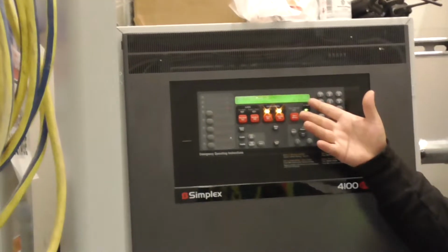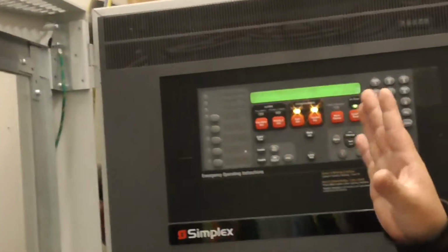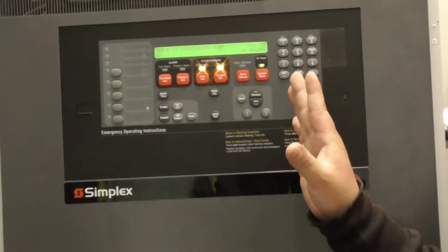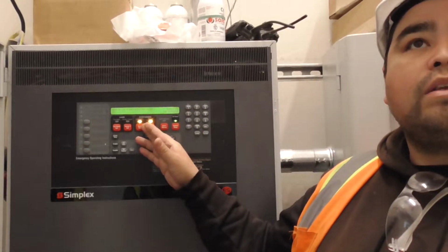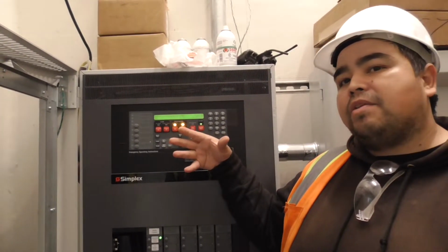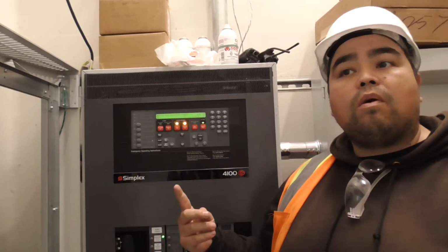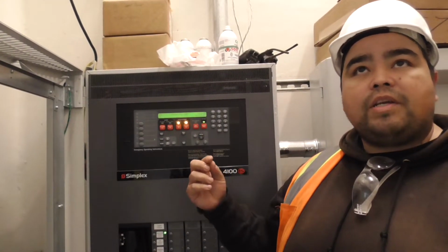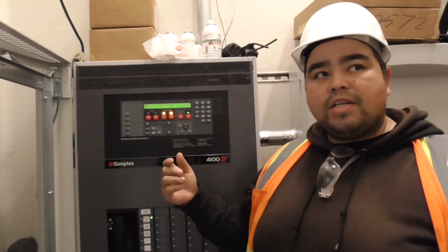Right? So trouble events are more like there's something wrong with the system, somebody took something down, could be a ground fault, an abnormal condition with the fire alarm panel. Supervisory condition would either be off normal, which means that somebody has a tamper, maybe someone closed a tamper somewhere in the building, or supervisory in a room. So all the rooms are latching supervisories.